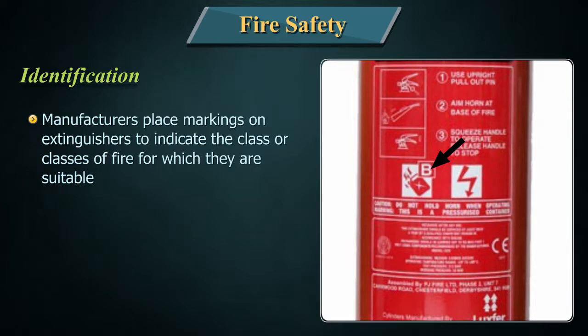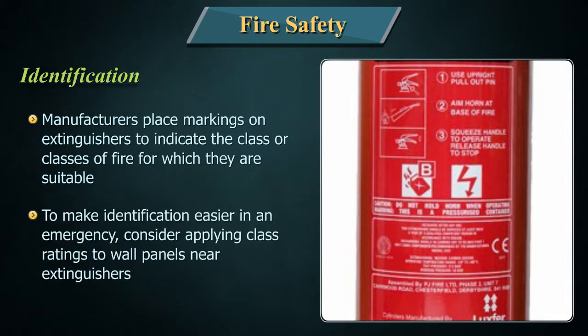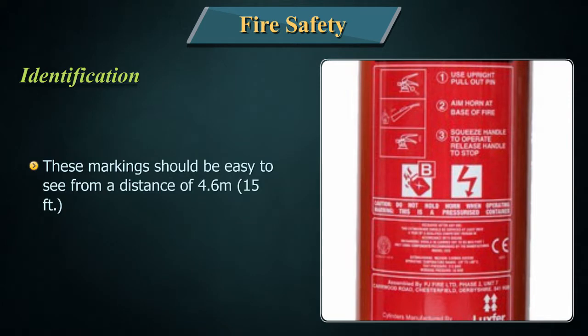Identification: Manufacturers place markings on extinguishers to indicate the class or classes of fire for which they are suitable. To make identification easier in an emergency, consider applying class ratings to wall panels near extinguishers. These markings should be easy to see from a distance of 4.6 meters, that is 15 feet.